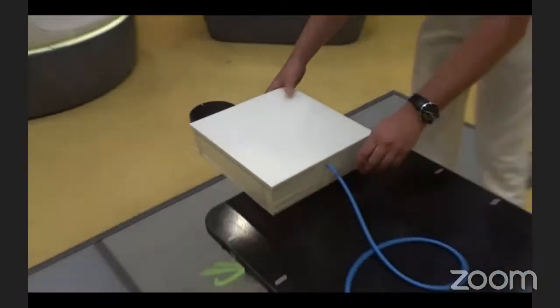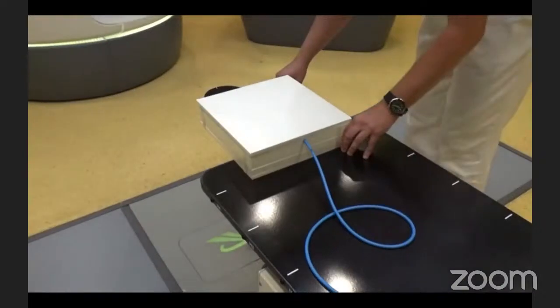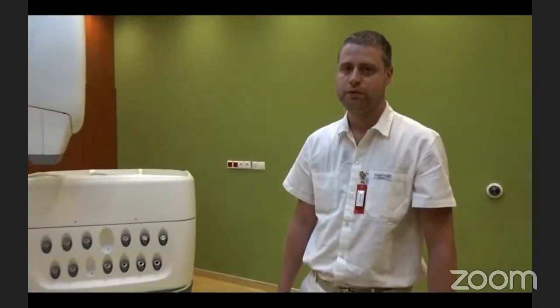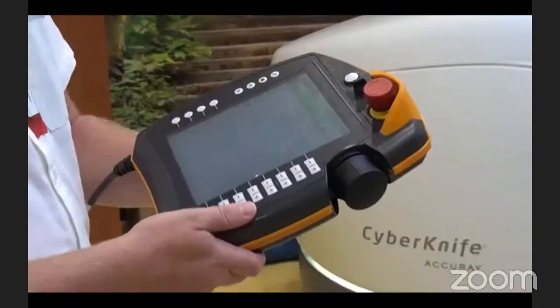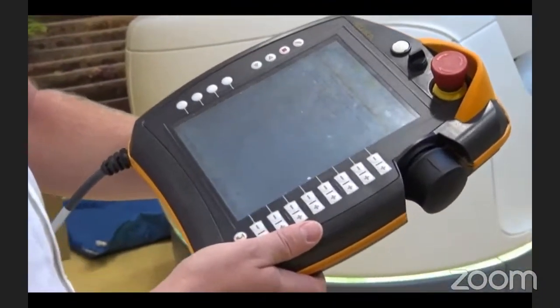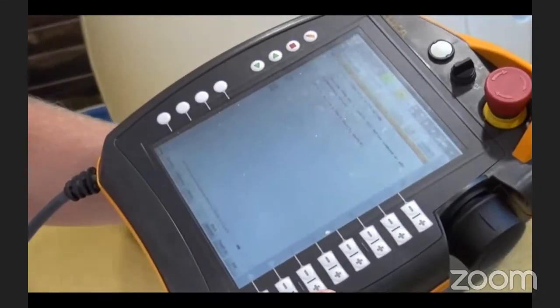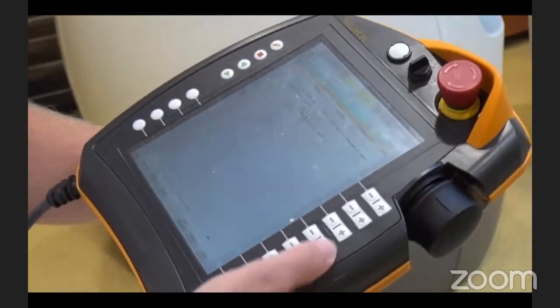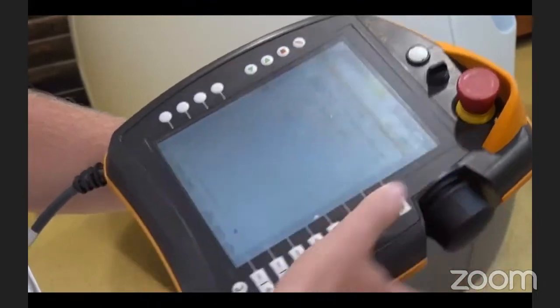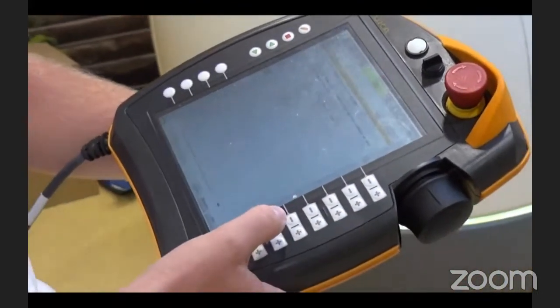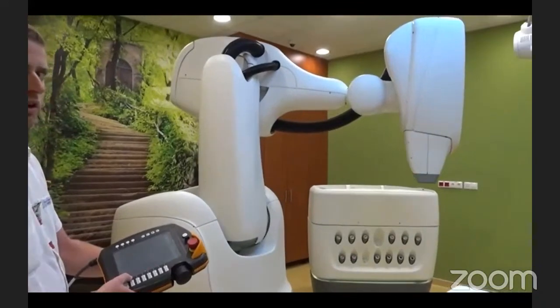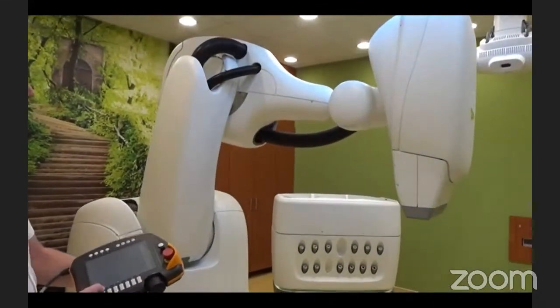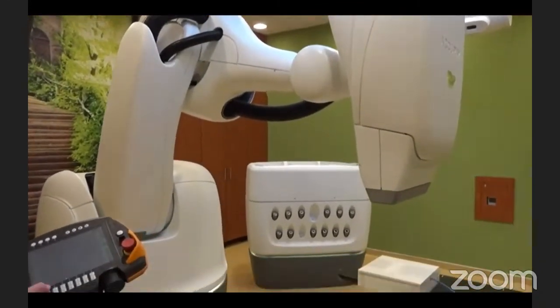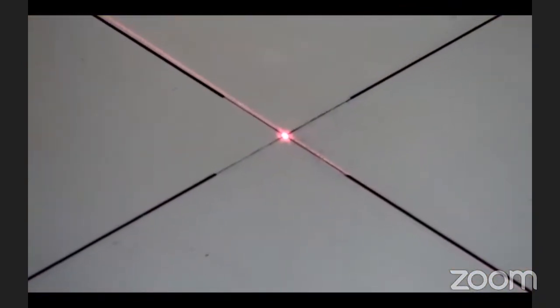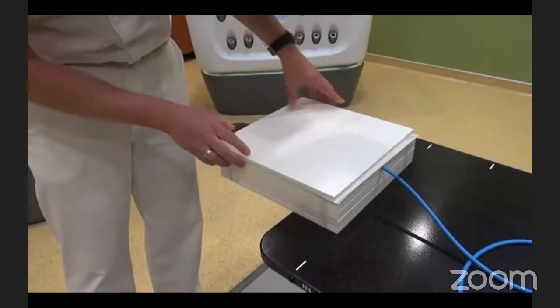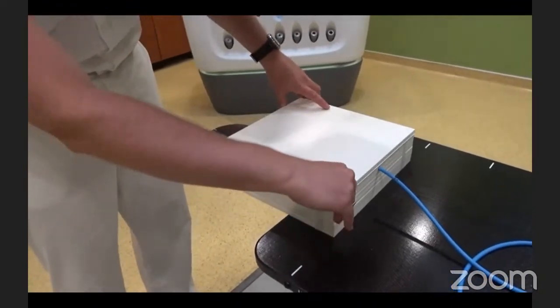And then we position this phantom below the linear accelerator. Into the middle of the field we position the ionization chamber. This is the manipulator, the hand pendant of the robot. With this we can drive the robot into the expected position. And we position the beam exactly above the ionization chamber. Then we put the final slab on to make the exact depth of the ionization chamber.